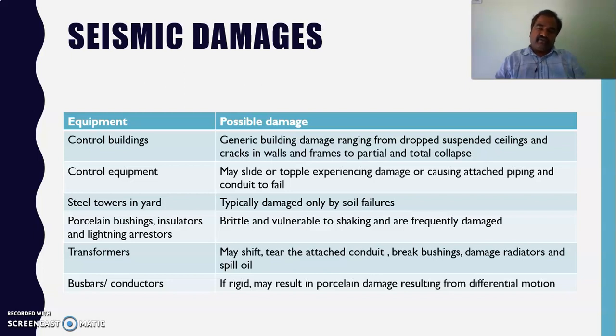There will be control equipment in these control substations. This control equipment may slide or topple, experiencing damage or causing attached piping and conduit to fail if it is not properly anchored.